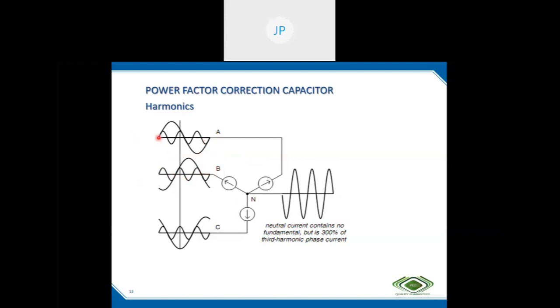That means they don't have any phase shift. Even though the currents have a 120-degree displacement, the third harmonic has 3 cycles per fundamental cycle. So all the third harmonic components are in phase. All three in-phase currents meet here, and the sum flows through the neutral. By Kirchhoff's current law, the node current should be 0, so all the current meeting here should go through the neutral.